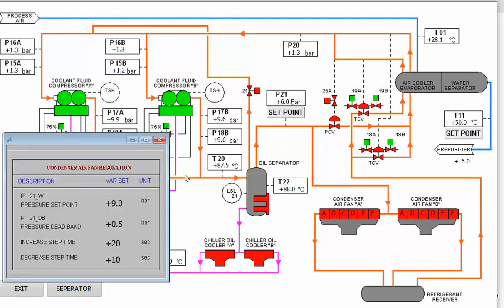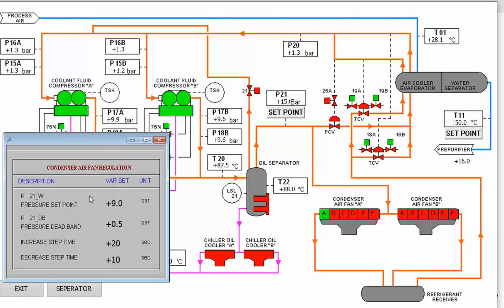The set point for pressure is 9. If during startup we have more refrigerant pressure, then we compare that to the set point. When the pressure is more than the set point plus half a deadband, every 20 seconds we increase the capacity. Increasing capacity means we will have more condenser air fans running.